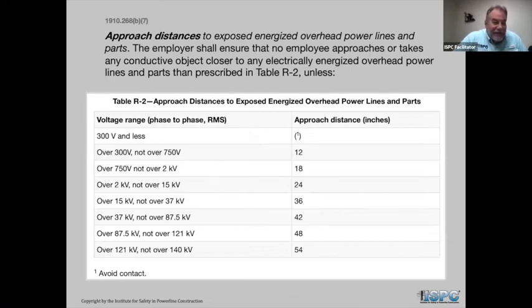Here's some of those distances. This is out of the 1910.268. 1910.269 is a little bit different. It just adds a couple more inches to it since 2014. OSHA has not really had a chance to go into here, but 750 volts to 2,000 volts is about 18 inches. Over 2,000 volts up to 15 kV is 2 feet.